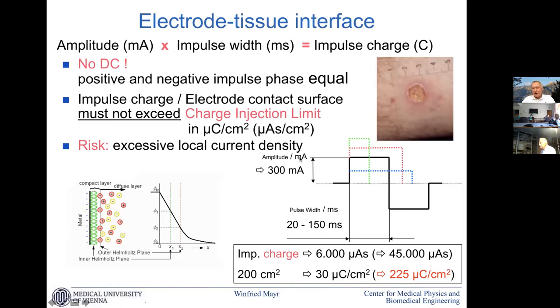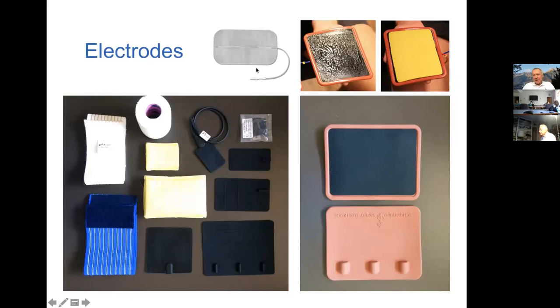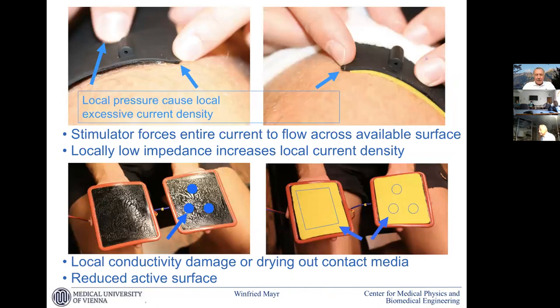When you have a high current density on the edge of an electrode, tissue damage can happen — and should be avoided by careful handling. For the big muscles we have large electrodes with gel or water contact. We developed safe electrodes with a non-conductive lid that prevents overloading at the tissue edges where most burns occur. The media can dry out and you can get higher current densities locally, so these are things to be avoided.